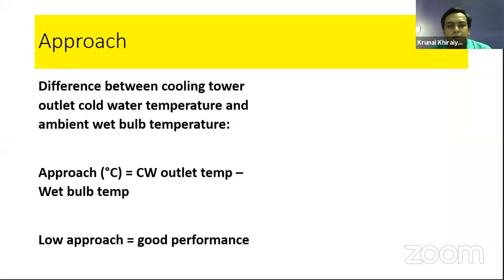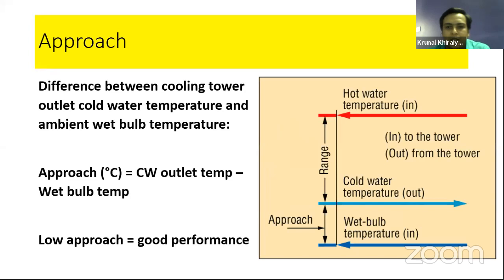Now, next is approach. Again, I'm using the same picture, the same schematic. Here, the difference between the light blue and dark blue is called the approach. So a low approach is good. See here, it is the reverse of the range. In range, if your range is high, then your performance is high. If the approach is low, the performance of the cooling tower is good. So this is the difference between range and approach.